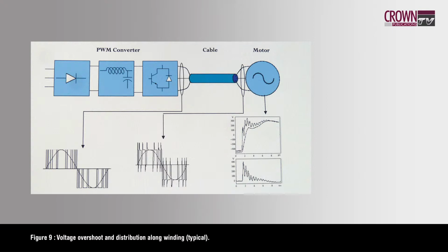Yes, the article that I'm trying to cover there is that we are getting partial discharges because you're getting extremely high voltages, but short pulses, depending on the inverter supply. The technique nowadays is to use IGBTs, which have a very fast, incredibly rapid switch. The switching time is now critical, combined with the cable length feeding the motor.